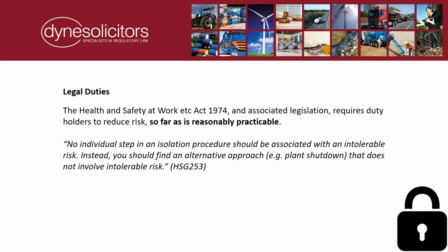This all falls within the concept of risk assessment. And I have mentioned HSG 253 because although this guidance is aimed principally at the oil and gas industries, the principles in the guidance are of general application for isolation. I simply wanted also to draw to everyone's attention that it may be safer to shut down the entire process line rather than an individual component of that process line, so taking the lowest risk option to comply with the reasonably practicable qualification. And I do recommend a read of HSG 253 because it does contain some very useful reference material on human factors, roles, responsibilities, training, competence, review and safe systems of work, because all these things are of general application.